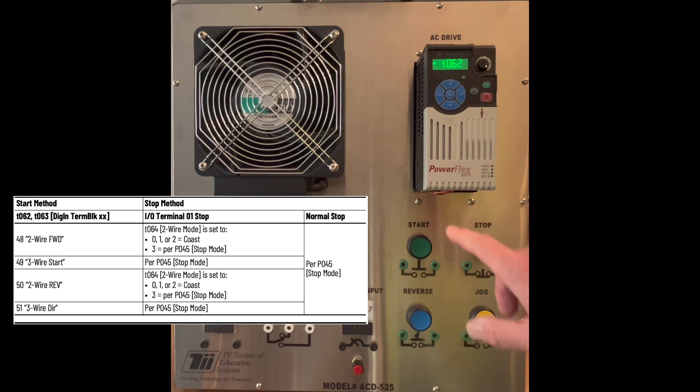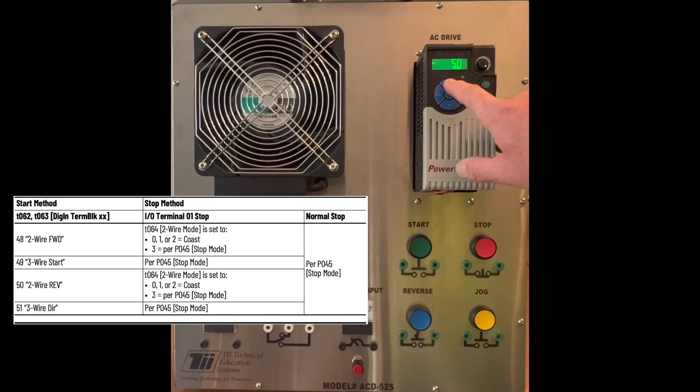We're going to hit enter again. Escape. Then we're going to enter into 63. T62 set the start button, and 63 will set the stop button, which is wired to this terminal. So we're going to hit select in here, and we're going to change this to 51. Hit enter again. Hit escape three times.